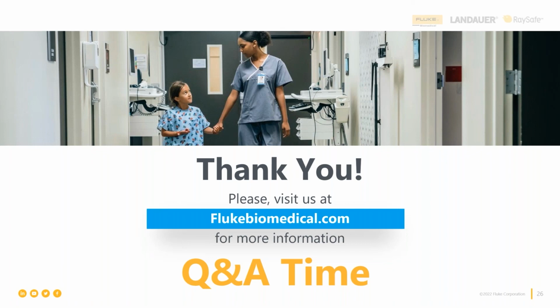Now, if what the person asking the question means is Class IP, internal power, then I can answer the question. That would be any medical device that is powered by its battery, and we need to do electrical leakage current when it's functioning on its battery, not through any battery charger or adapter going to mains. There are a host of them: defibrillators, for example, infusion pumps, even some ventilators that are battery powered, especially for transport. Suction pumps intended for use in transport often are battery powered. So anything with a battery in it that is a medical device that's going to be used in clinical situations still needs to be tested. And that's Class IP, not Class 3.